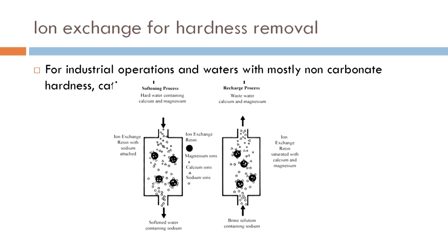So, what do we have out here? We have hard water containing calcium and magnesium coming in. We have the ion exchange resin, upon which you have sodium initially present, and calcium and magnesium, with greater charge density, are going to displace Na+, that is why they are called cation exchangers. Ca2+ and Mg2+ are going to be adsorbed onto this particular ion exchanger and removed.